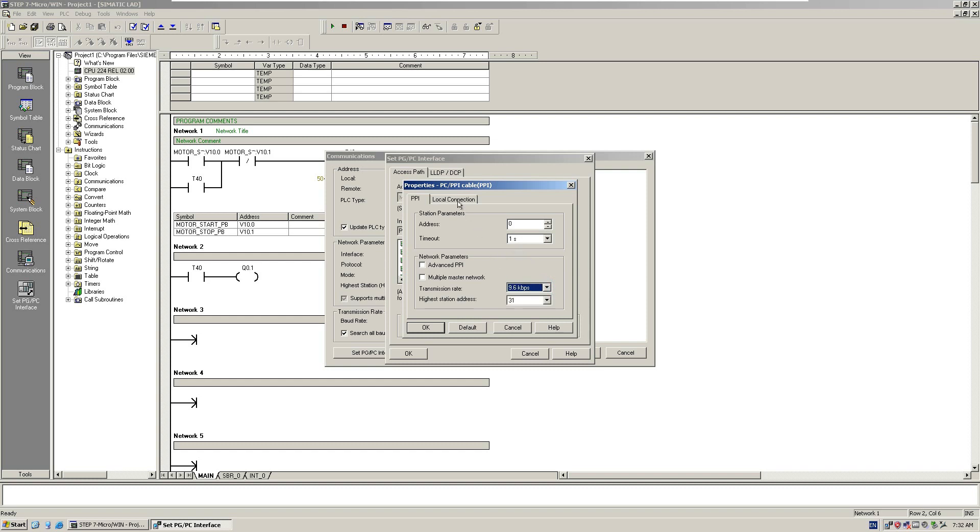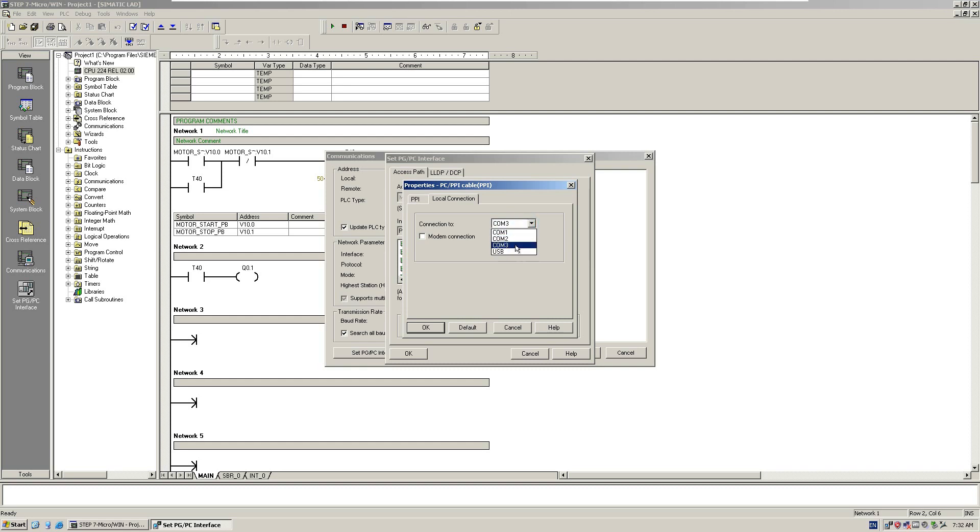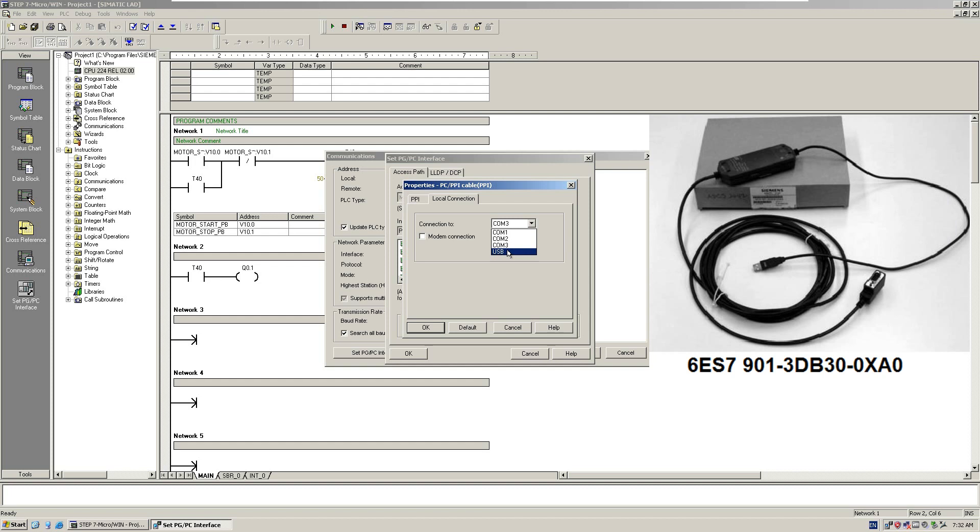Let's go to local connection. Here is a very important setting. Because our Windows system images this cable to port 3, COM port 3, from here I will select COM port 3. Maybe someone will ask why not use USB. This USB selection will only be selected if we use a Siemens adapter, where one side is USB and another side is RS-485.